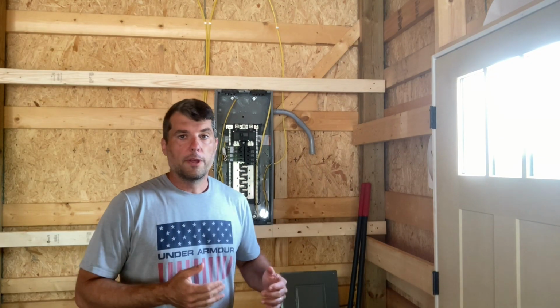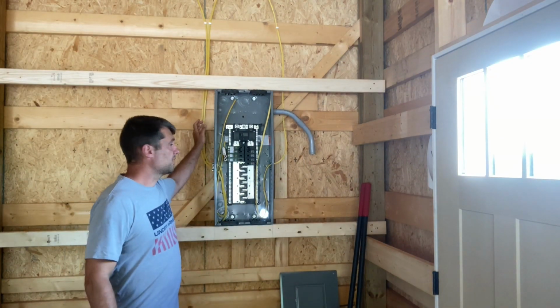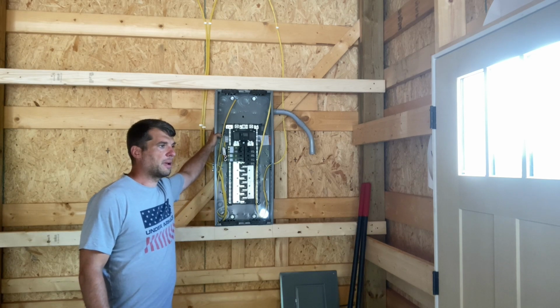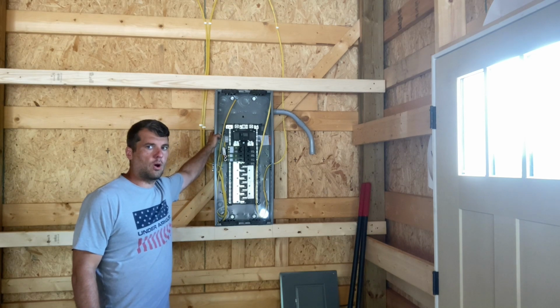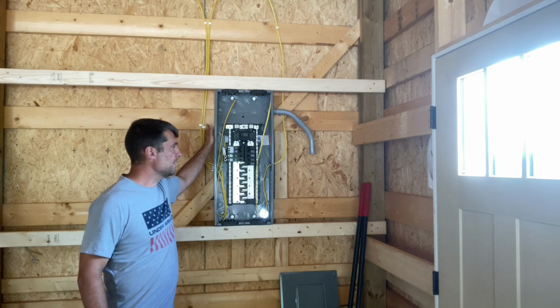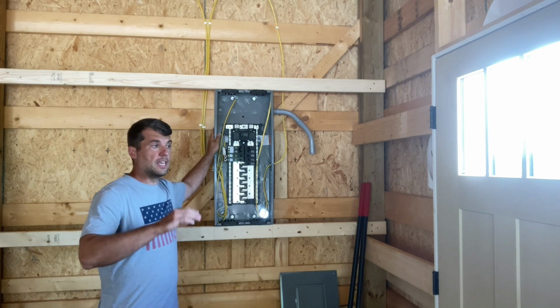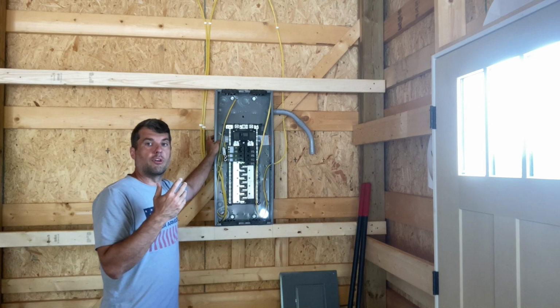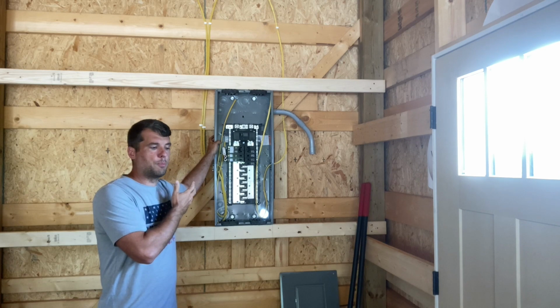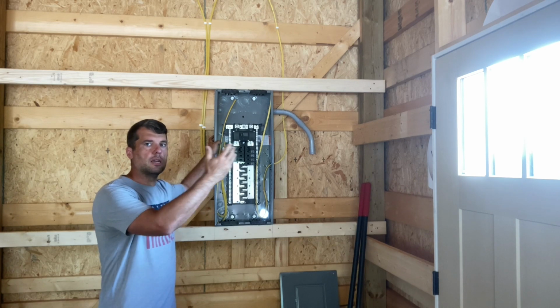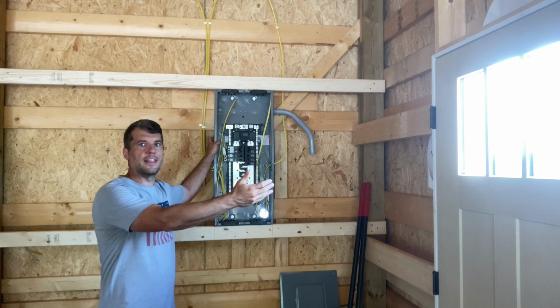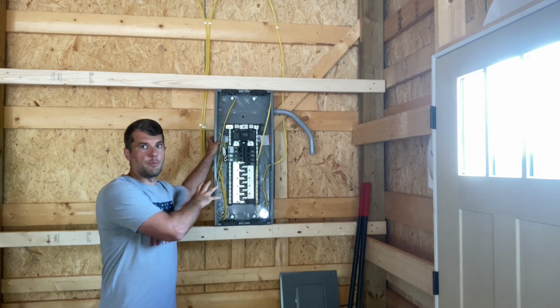I'm going to start with the main breaker panel. This is my 200 amp service panel, and right now I'm planning on this being the main panel for the entire residence. So my main breaker panel will be in here, and I'm actually going to feed a sub panel that I'm going to put in the house from this breaker panel.